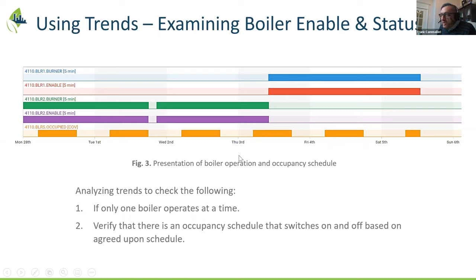So again, this is just telling you, yes, only one boiler operates at one time. And making sure the occupant schedule is actually switching between occupied and unoccupied. This is occupied, this is unoccupied, again occupied, unoccupied, and you can see it's consistently happening. On the weekend, it's a little bit longer, the unoccupied periods, which makes sense. This is just another example of how you verify that.